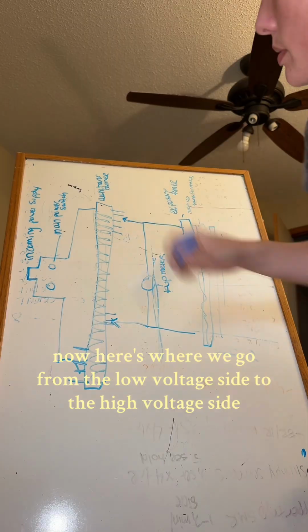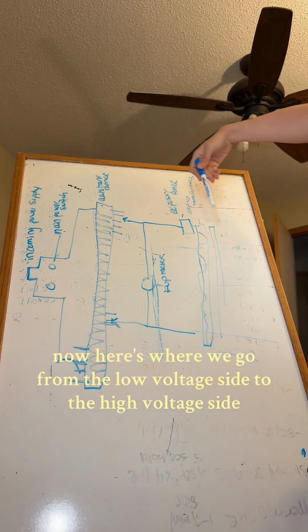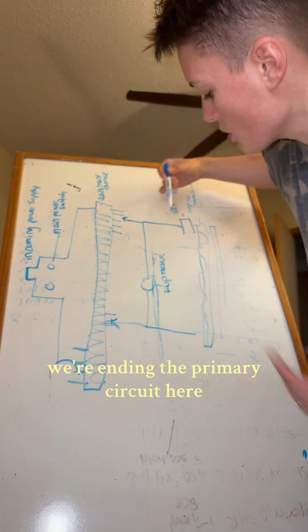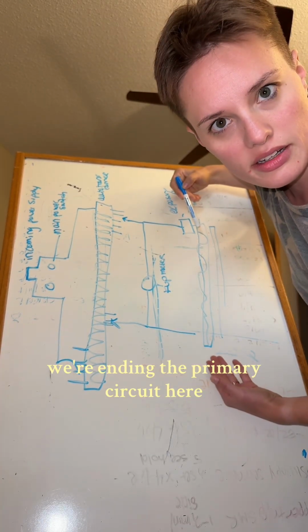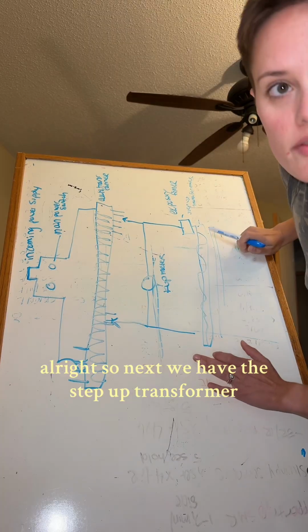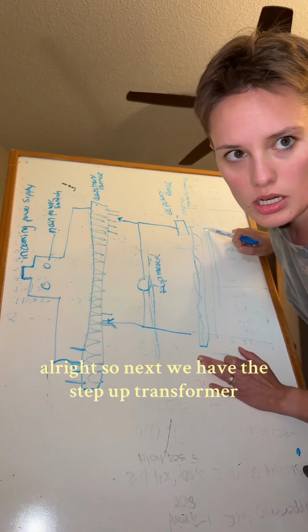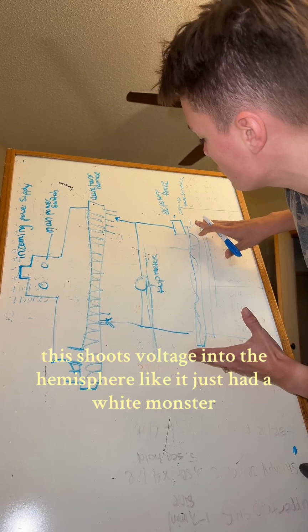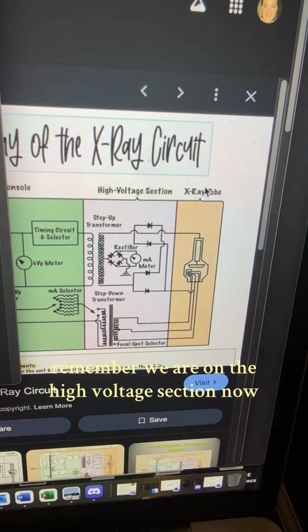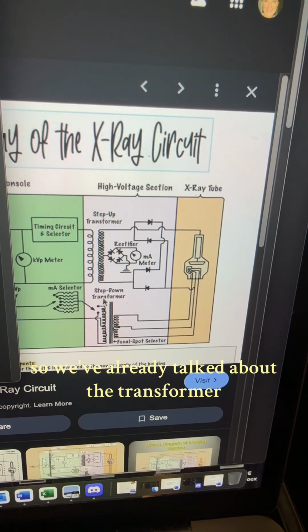Now, here's where we go from the low voltage side to the high voltage side. We're ending the primary circuit here. Alright? So next we have the step-up transformer. This shoots voltage into the hemisphere like it just had a Monster. Not only am I terrible at drawing, my whiteboard also sucks, so we're just gonna do this the old-fashioned way. Okay, remember, we are on the high voltage section now, so we've already talked about the transformer.